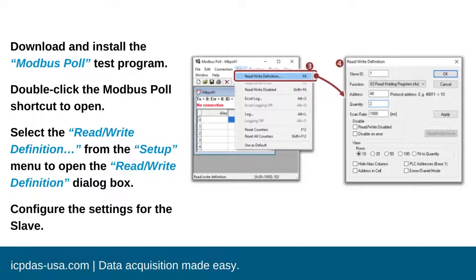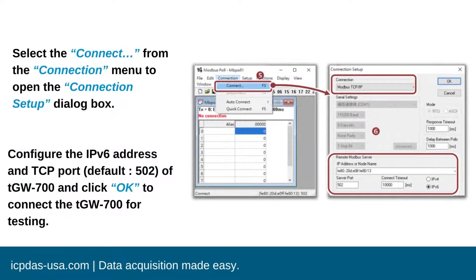To self-test, download the Modbus Poll Test Program. The link is available in the description box of this video. Open the program and select the ReadWrite Definition from the Setup menu to open the ReadWrite Definition dialog box. Configure the settings for the slave device — the settings will vary depending on your Modbus device. Select the Connect option from the Connection menu to open the Connection Setup dialog box. Configure the IPv6 address and TCP port of the TGW-700 and click OK to connect it for testing.